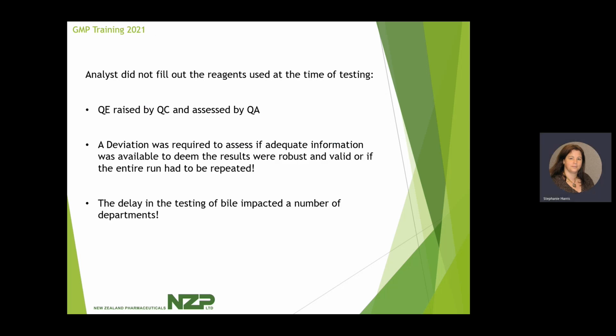The analyst did not fill out the reagents used at the time of testing. Therefore, a QE had to be raised by QC and assessed by QA. A deviation was required to assess if adequate information was available to deem the results were robust and valid, or if the entire HPLC run had to be repeated.